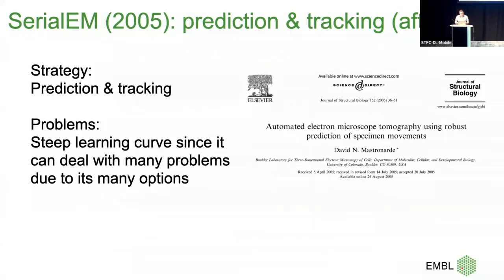In 2005, David Mastronarde came up with prediction, tracking before, and tracking after — combining everything. You tilt, you have a choice to do tracking, or just prediction. Once you have four points it predicts the next one; if the error margin exceeds a certain amount it decides to take a tracking image. That combination worked really well on every stage — that's the strength of SerialEM: it doesn't matter how bad your stage is or how poorly the service engineer left the alignment.